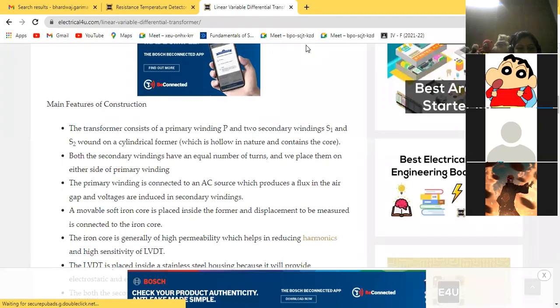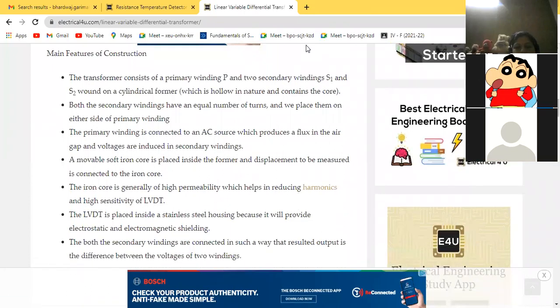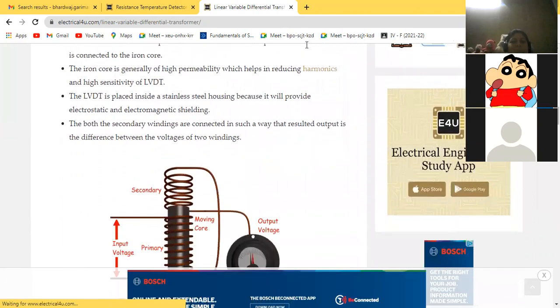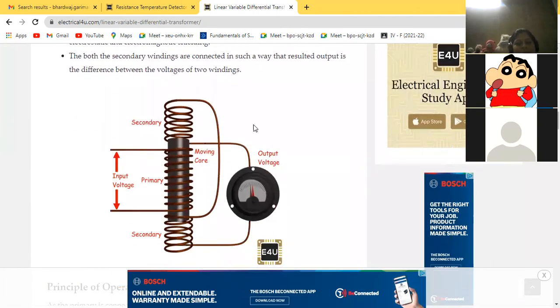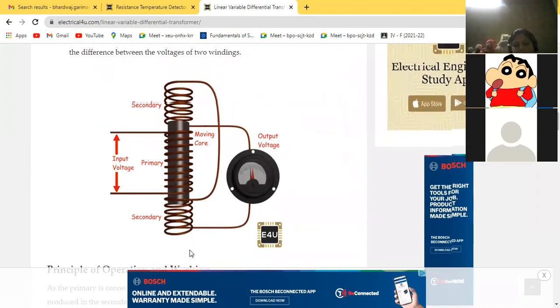A movable soft iron core is placed inside the former, and the displacement to be measured is connected to the iron core. The iron core is generally of high permeability, which helps in reducing harmonics and gives high sensitivity of the LVDT. The LVDT is placed inside a stainless steel housing because it provides electrostatic and electromagnetic shielding. Both the secondary windings are connected in such a way that the resulting output is the difference between the voltages of the two windings. You can see here the primary winding and the two secondary windings. The number of turns in both the secondary windings is the same.